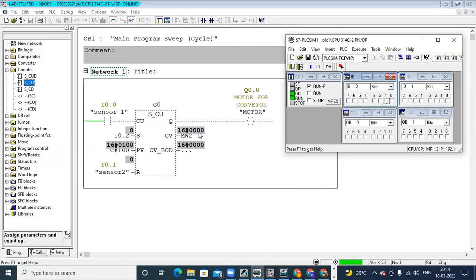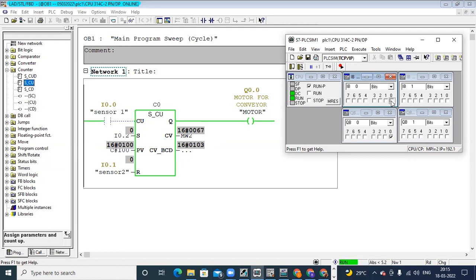Right now in CV the value is zero. When I give input I0.2, the value 100 is moved to MW2. Here it is showing 64 — that is the hexadecimal value — whereas below in CV underscore BCD it is in BCD format. Now I remove the set input — the value is set to 100. When I give the CU input, it starts counting from 101. This is optional — if you want to start from some middle value for counting, you need to use set and PV; otherwise it is not mandatory.